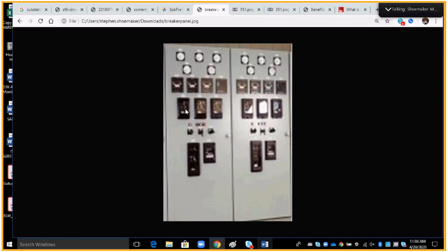So in essence, what I can do here is I can set, and this is typical in distribution systems. We'll talk a little bit more in depth about fuse saving and a fuse blowing scheme when we get to the fusing part out there in the field, but that's a different subject. They're going to set up their relays to be first instantaneous and then timed.